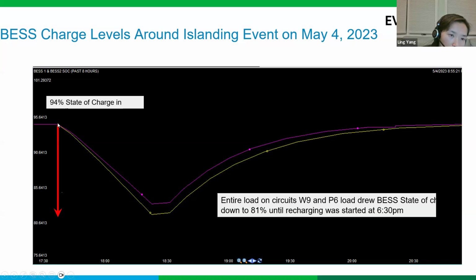It was about a 94% state of charge before the event happened, and it dropped to somewhere around 90, 92, 82, 81, 82% after the event was cleared. And then the state of charge of the battery started charging with resistance, slightly charging, with the state of charge going up.